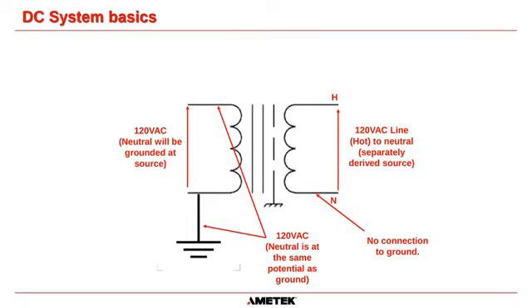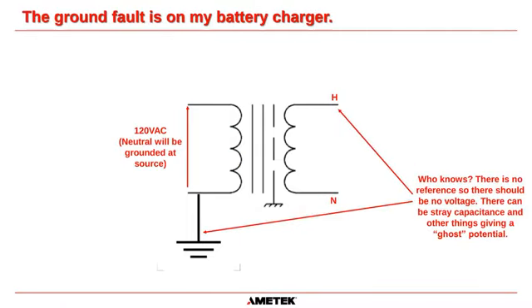So if we use a Fluke and we go between live and neutral or live and ground, we're going to get 120 volts AC if it is an outlet in your house. Okay, because that's what we use in North America, 120 volts AC, because neutral is at the same potential as ground. But on the secondary side of this transformer, yes, you will get 120 volts between hot and neutral, or live and neutral, however you want to call it. But because there is no connection to ground, if you go between the hot cable and ground, there should be no voltage. Okay, because there is no reference.